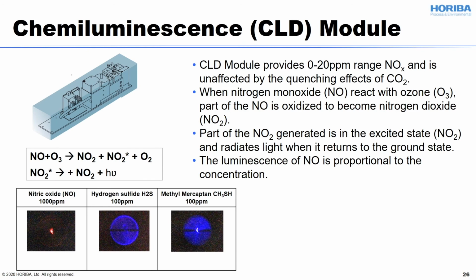Alright, another measurement module: chemiluminescence. The chemiluminescence module provides 0 to 20 ppm NOx concentration, and it is not affected by the quenching effect of CO2. Actually, quenching is a well-known problem of chemiluminescence, but we use dilution air to dilute the sample gas, and this helps cancel the effect from quenching of CO2. Chemiluminescence works when NO reacts with ozone. Part of the NO is oxidized to become nitrogen dioxide, which is NO2. Part of the NO2 generated is in an excited state. The luminescence is proportional to the NO concentration. This is how we measure the NO.